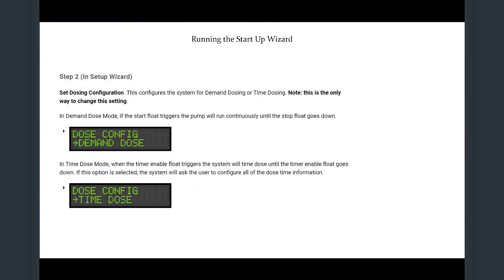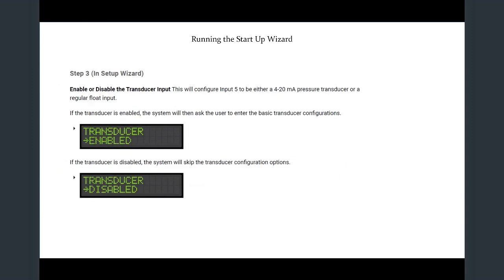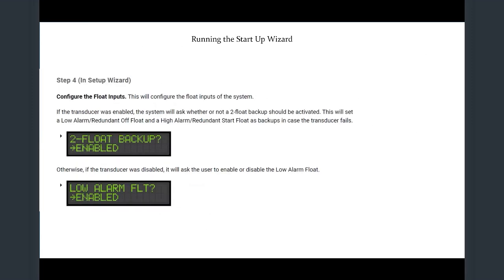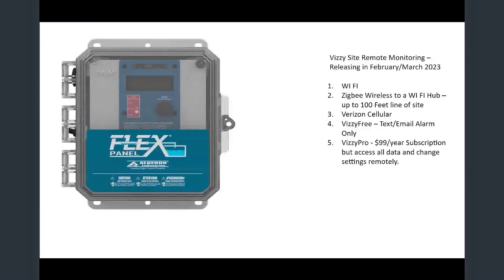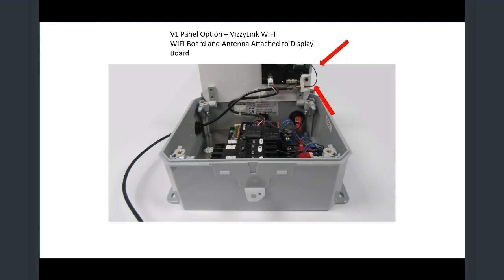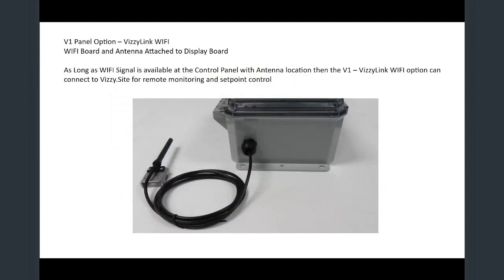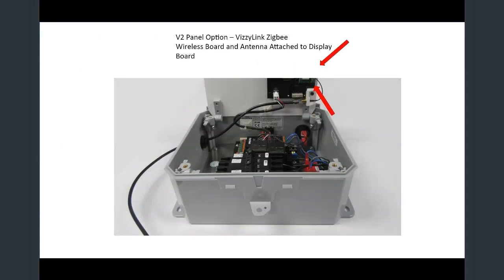On the Flex, there's a setup wizard, so it'll go in there and ask you, are you doing time dose? Are you doing demand dose? Do you want to enable or disable your transducer? Do you want a 2-float backup? Do you want to enable or disable your low-level alarm float? And this talks about our Wi-Fi, Zigbee, or cellular.